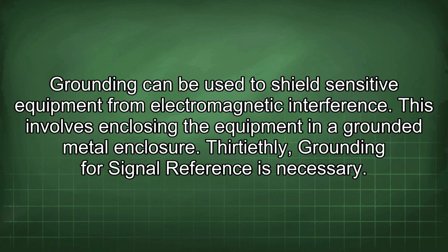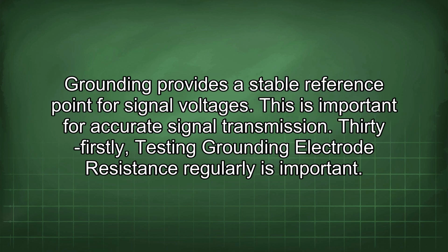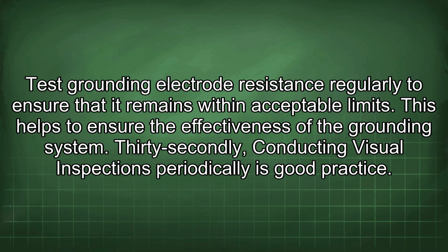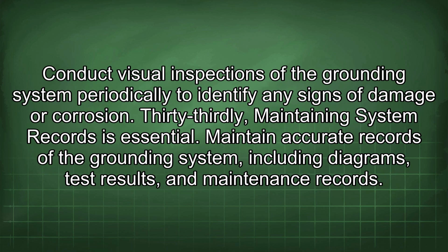Thirtiethly, grounding for signal reference is necessary. Grounding provides a stable reference point for signal voltages. This is important for accurate signal transmission. Thirty-firstly, testing grounding electrode resistance regularly is important. Test grounding electrode resistance regularly to ensure that it remains within acceptable limits. This helps to ensure the effectiveness of the grounding system. Thirty-secondly, conducting visual inspections periodically is good practice. Conduct visual inspections of the grounding system periodically to identify any signs of damage or corrosion.